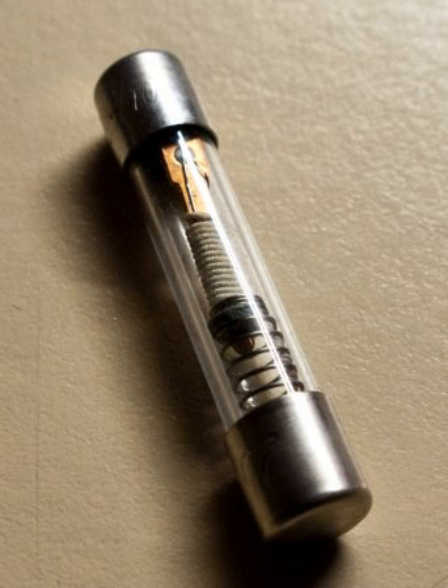Topic: Breaking capacity. The breaking capacity is the maximum current that can safely be interrupted by the fuse. This should be higher than the prospective short circuit current. Miniature fuses may have an interrupting rating only 10 times their rated current. Some fuses are designated high rupture capacity (HRC) and are usually filled with sand or a similar material.